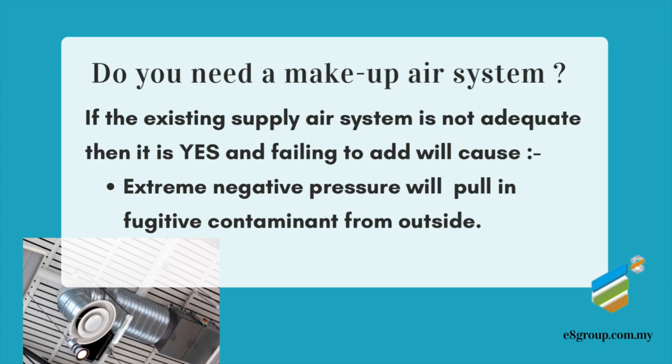When you have a local exhaust ventilation system designed for 3000 or 2000 CFM and you do not have an adequate amount of air coming in, you can maintain 10 to 15% vacuum. But if you maintain 100% vacuum by not installing any makeup air at all, that fan is not going to function. It's not going to pull that 3000 CFM which you have designed for. There's no air to pull. This is another cardinal, very big error a lot of system providers make when they install a local exhaust ventilation system. They decide not to add makeup air, not to add a supply air system. So the room becomes under extreme vacuum and infiltration.